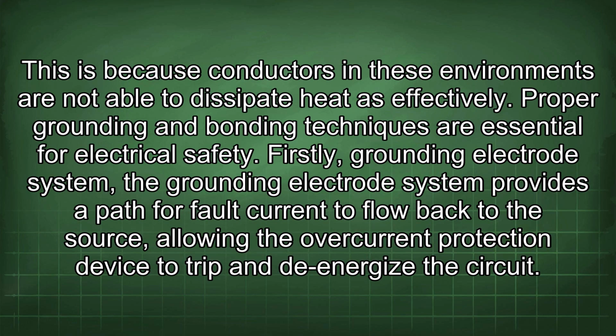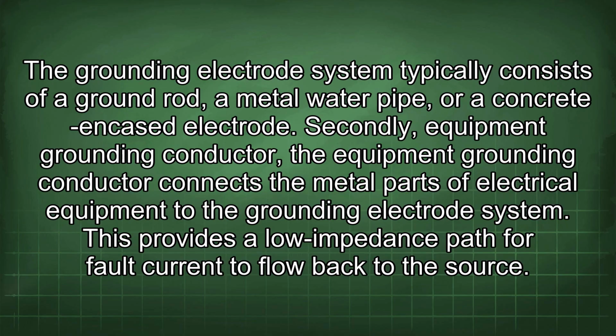Proper grounding and bonding techniques are essential for electrical safety. Firstly, grounding electrode system. The grounding electrode system provides a path for fault current to flow back to the source, allowing the overcurrent protection device to trip and de-energize the circuit. The grounding electrode system typically consists of a ground rod, a metal water pipe, or a concrete encased electrode.